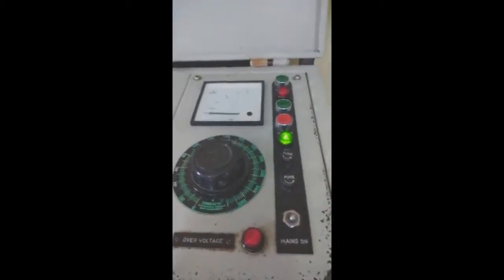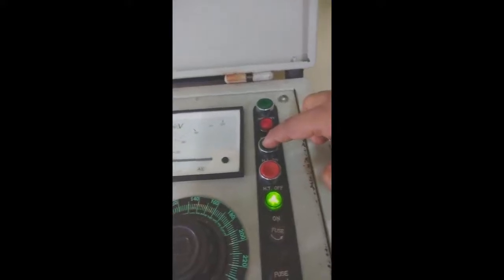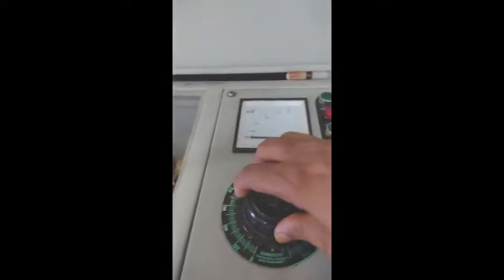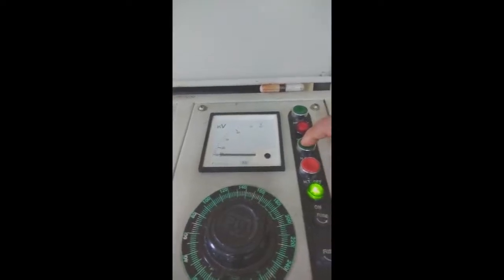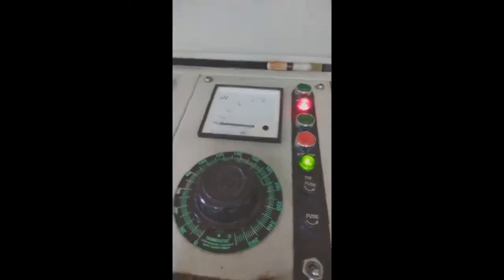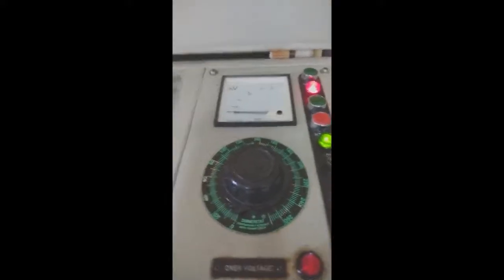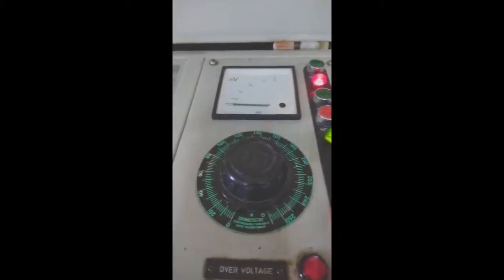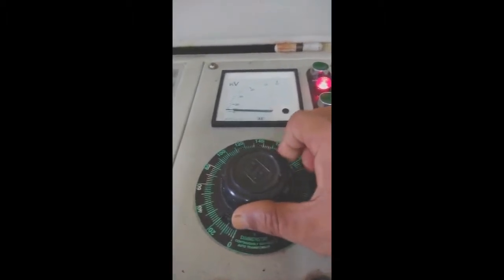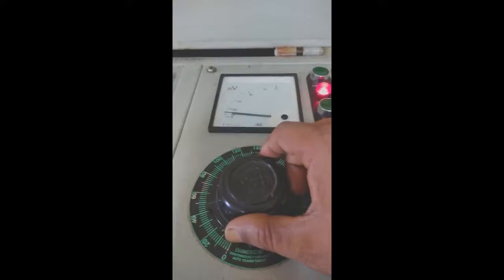Now we will shut this chamber and power on. This is the HT button. We will press it. This will be in 0 position, and we will press this. Then it is on, and then we will gradually increase the voltage of these two electrodes. The increase of voltage will be at a rate of 2 kV per second, that is, slowly increase the voltage.